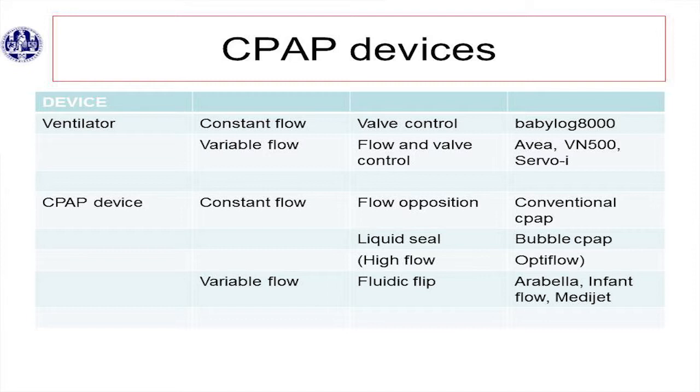The CPAP devices. There are different ways to divide them. The ventilator can give CPAP, and so can dedicated CPAP devices. The ventilator can be divided by whether it gives constant flow — controlled by a valve based on flow or position — or variable flow. The old baby log and the infant star give constant flow. With constant flow, if the baby requires more flow during inspiration, you get some flow starvation — that's a disadvantage. And if you breathe out, you breathe against the flow, which increases the burden of breathing, theoretically. Variable flow responds to demand, with servo-controlled valves — that's what our Avea and the VN500 do.